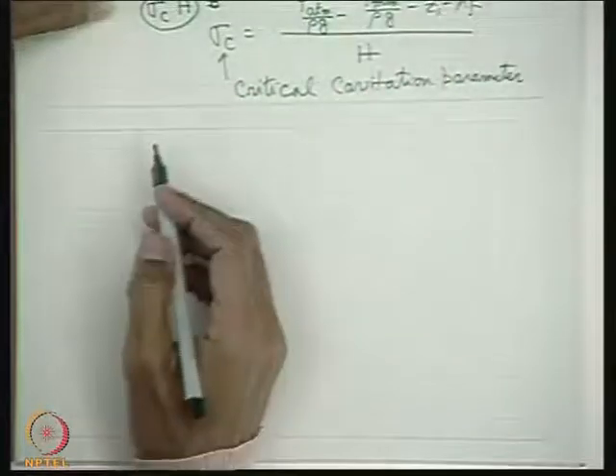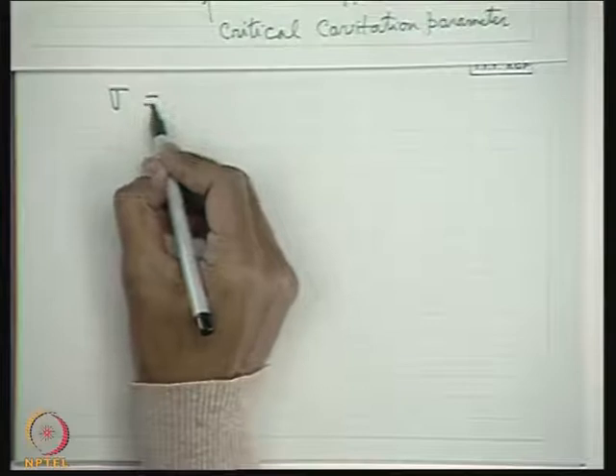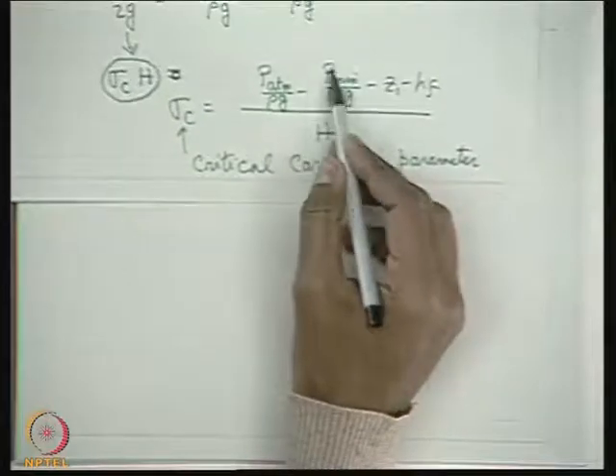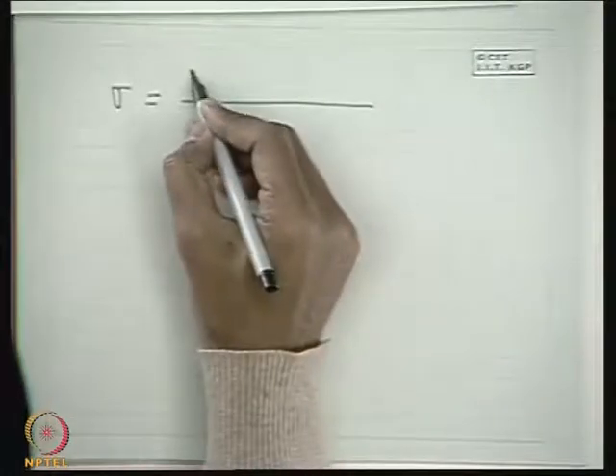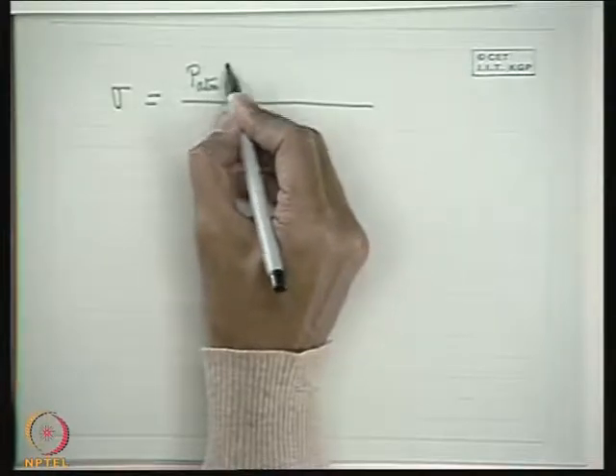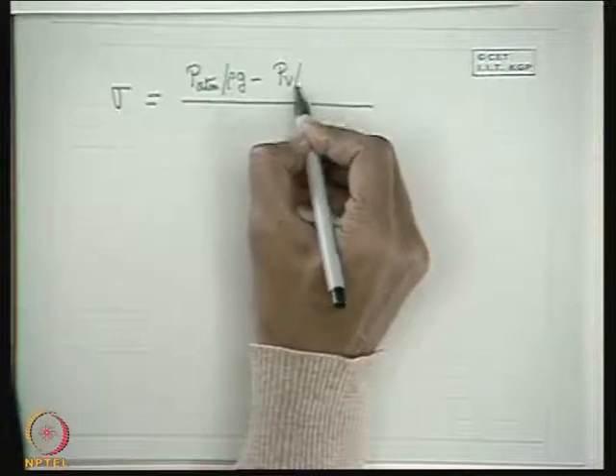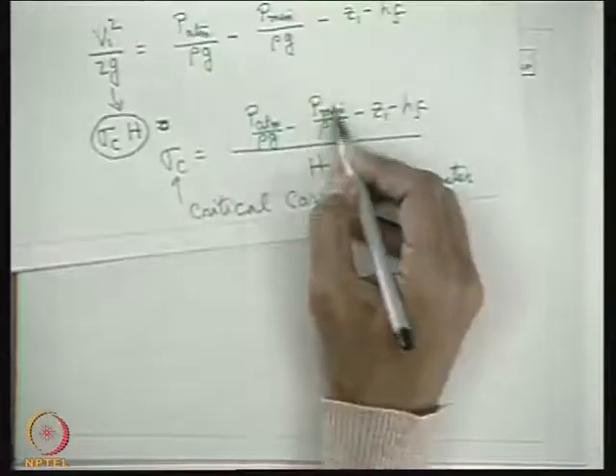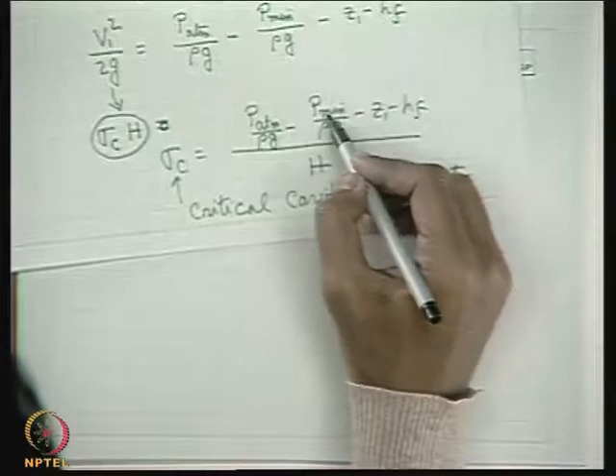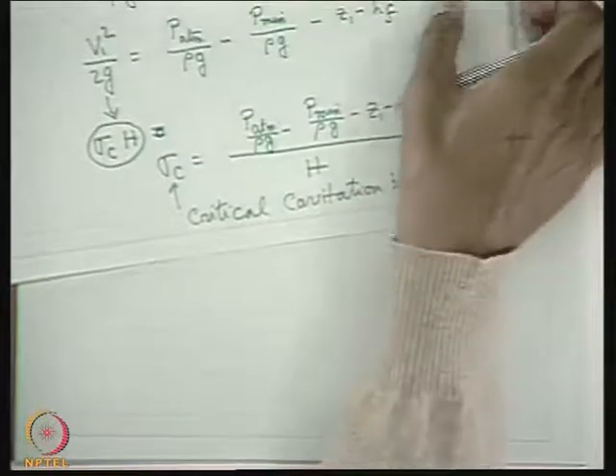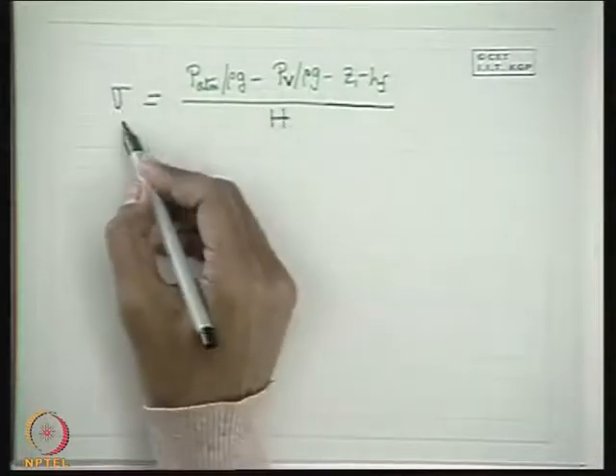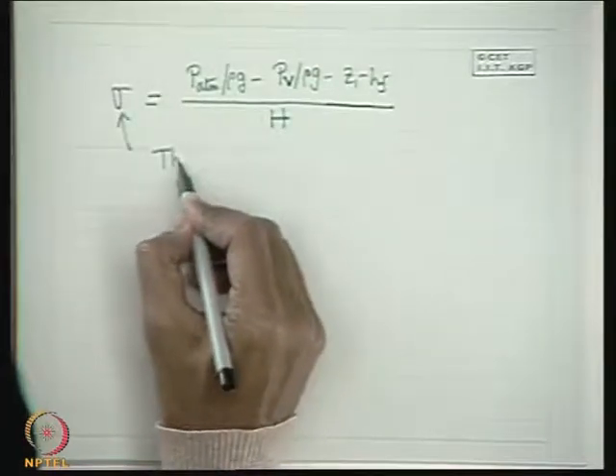Similarly, we can define the Thomas cavitation parameter σ, where the minimum pressure is set equal to the vapor pressure p_v of the liquid at the working temperature — which is the minimum allowable pressure in the entire hydraulic circuit of the pump. Substituting p_min = p_v gives the Thomas cavitation parameter, analogous to what was done for turbines.